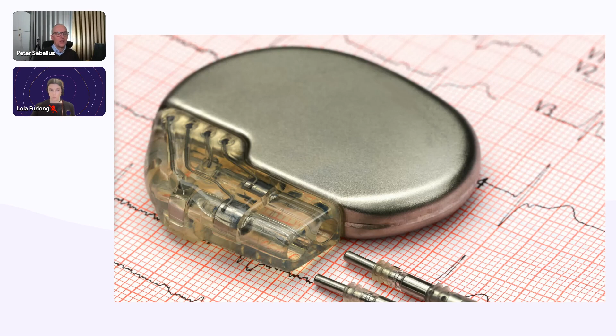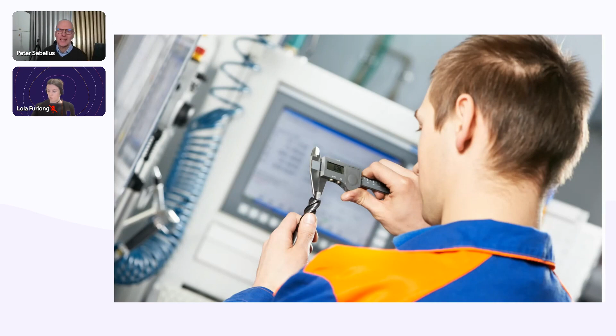There is one more situation, and that is if you're a contract manufacturer and you don't have the necessary information to estimate the risk, or you might not even know what the hazardous situation would be because you don't know the clinical consequences of a failure or a fault. Well, I regret to say that it's quite common that contract manufacturers are never given that information. So they can look at deviations from the spec, but do not know what harm it will cause. The problem with that is obviously that the priorities and risk evaluation might be completely off. This even happens sometimes with internal production, where the production department never gets that information. So if you are in production and you do not get that information on the clinical consequences of various failures or hazardous situations, then FMEA is a good fallback position. However, that obviously assumes that someone picks up the results from the FMEA in the ISO 14971 product safety risk management process, so that those risks are also found there.